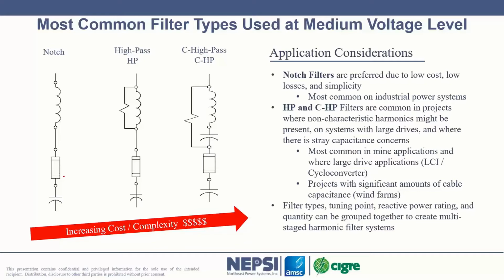We have seen that. Whenever you install filters on a system, you must consider the entire system, the system as a whole. And I don't have a whole lot of time to get to it, but oftentimes you have filters tuned to different frequencies at different locations. When you inject harmonic current into the network and you have the two filter systems side by side, you can enter a situation where you actually have some resonance amplification between the filters. So it's important that whenever you do harmonic analysis, you ask the questions, are there other harmonic filters nearby? They must be modeled. Are there other capacitor banks is even more important.